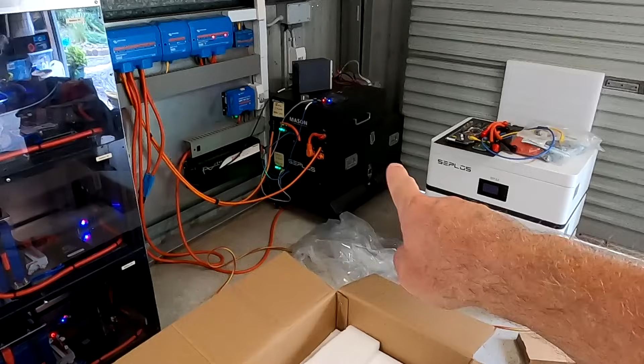Because some people criticized me because I never did this, I always only paralleled a 200 amp BMS and a 100 amp BMS from Seplos together. And this is not recommended by Seplos because the communication doesn't actually transfer over the capacity of the second battery. So the master always assumes the second battery is as big as the master, which in this case is wrong. So they only recommend using the same sort of BMSs and batteries and paralleling them together, which doesn't make sense.